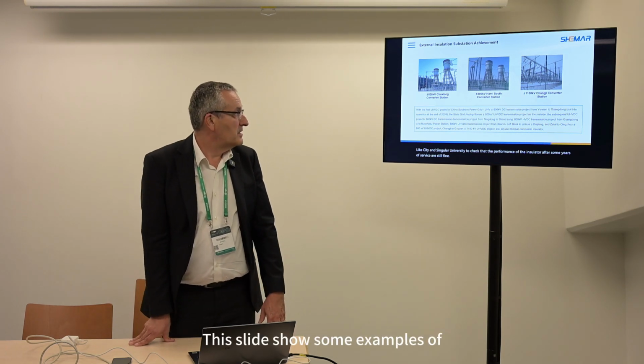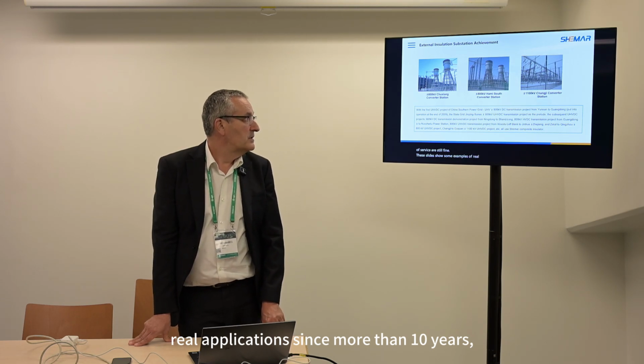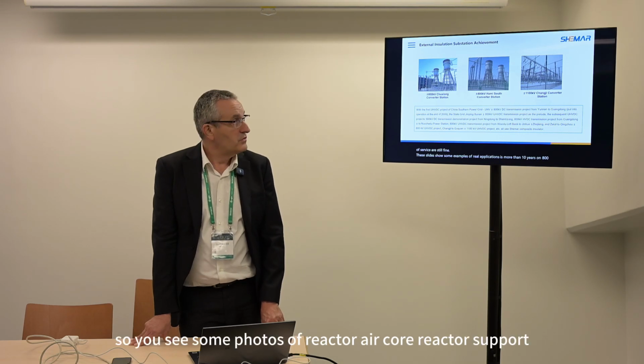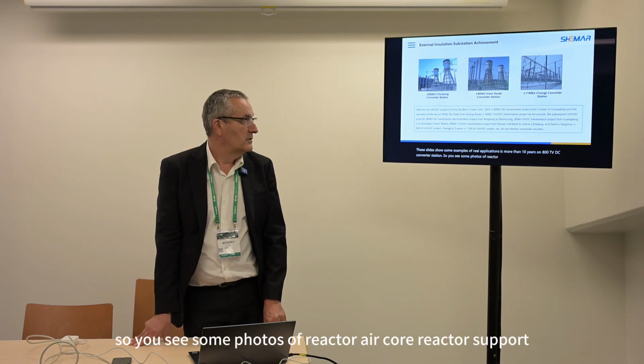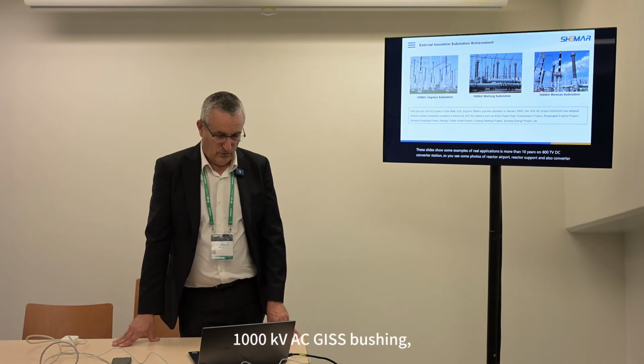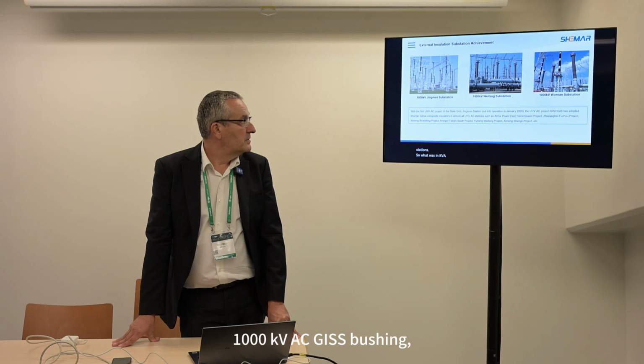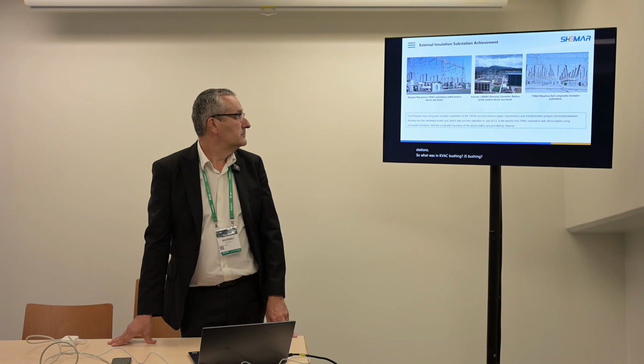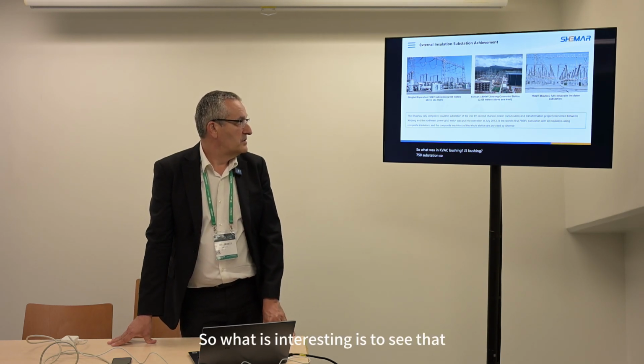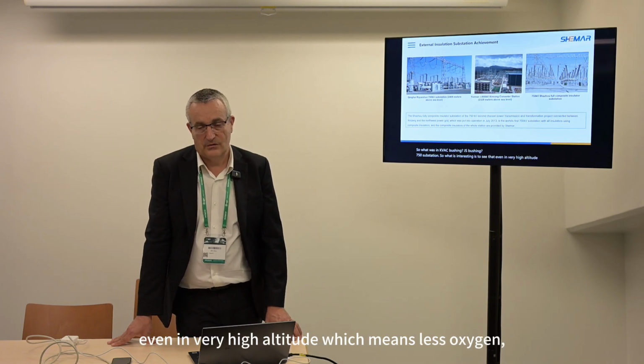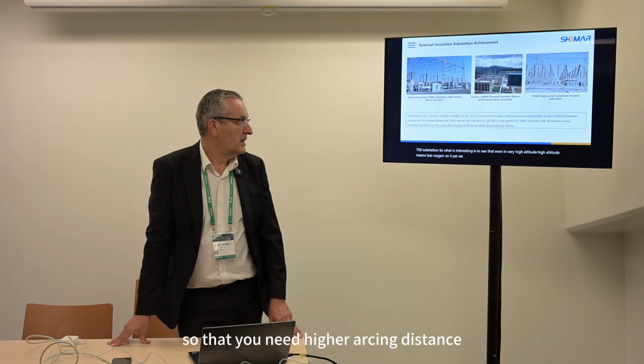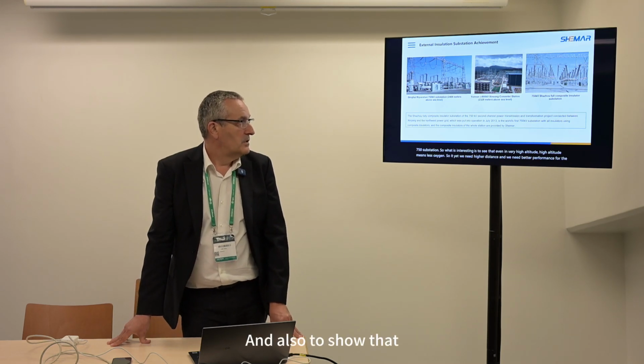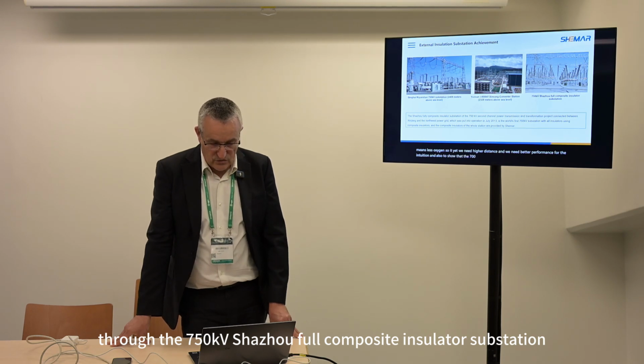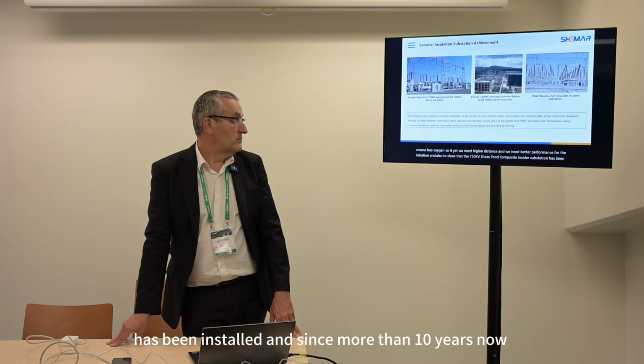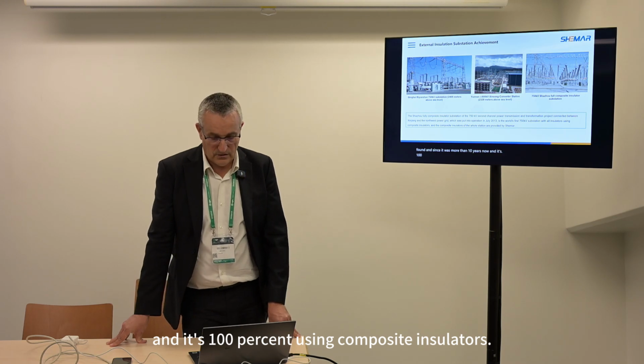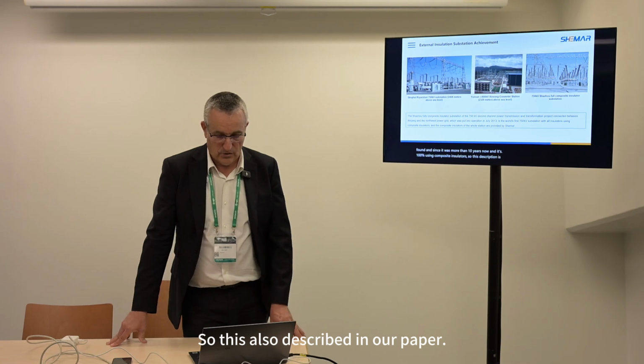These slides show some examples of real applications for more than 10 years on 800 kV DC converter stations. You see some photos of reactors, air core reactor supports, and also converter stations, 1000 kV AC bushing, GIS bushing, 750 kV substations. What is interesting is that even at very high altitude, which means less oxygen, you need a higher arcing distance and better insulation performance. It also shows that the 750 kV Shazhou full composite insulator substation has been installed for more than 10 years now, and it is 100% using composite insulators. This is also described in our paper.